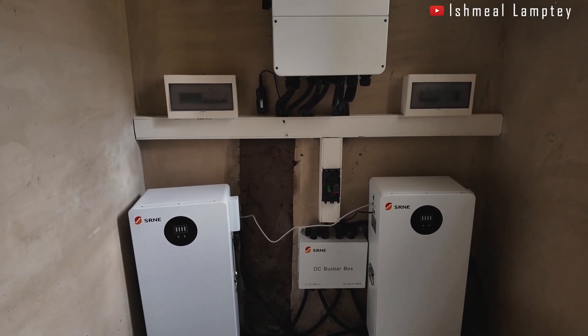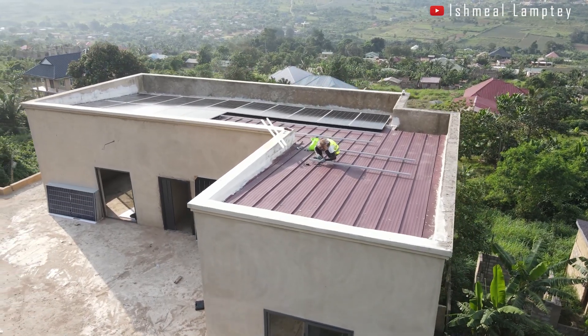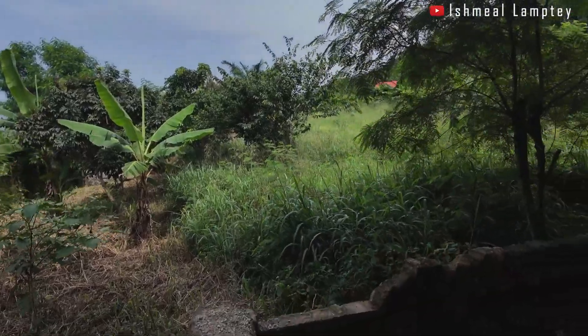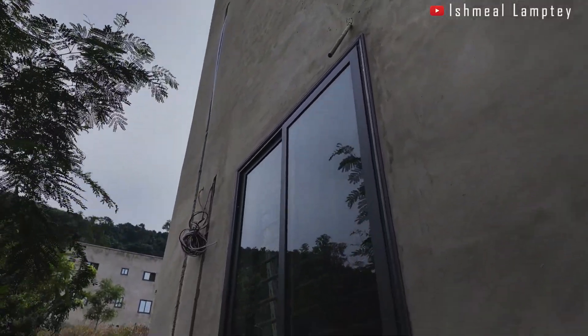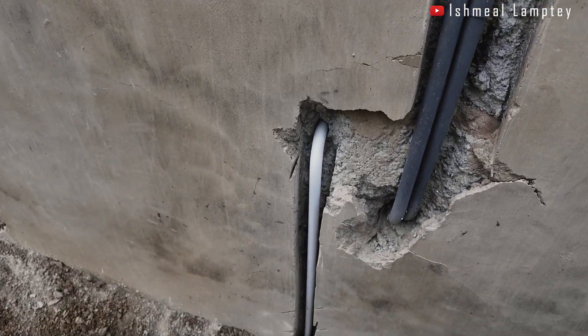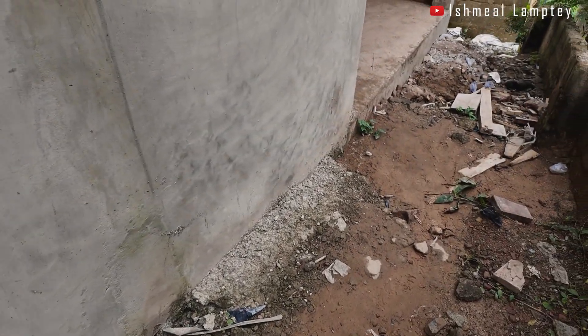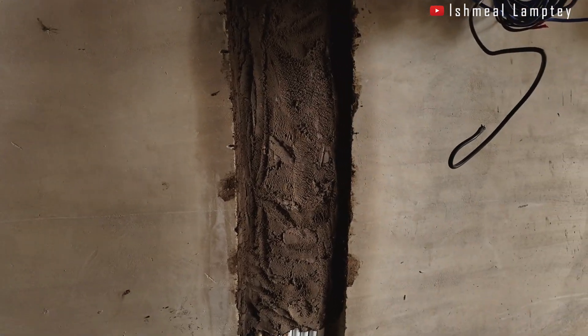It took us three days to complete this. Day one, we started with the panels. Day two, we did all the cutting and passing of pipes, including mounting a scaffold to cut all the way from the first floor outside — you can see the cuts with our pipes running all the way down. We also had to cut a point to bury an independent earth, as we always install our own independent earth rather than connecting to the existing one to avoid problems.